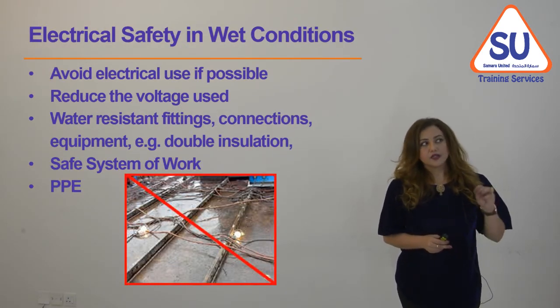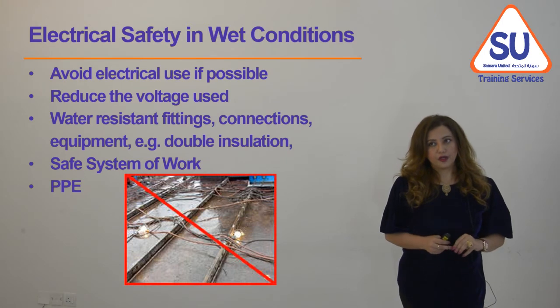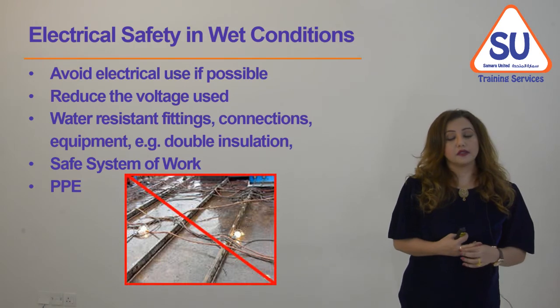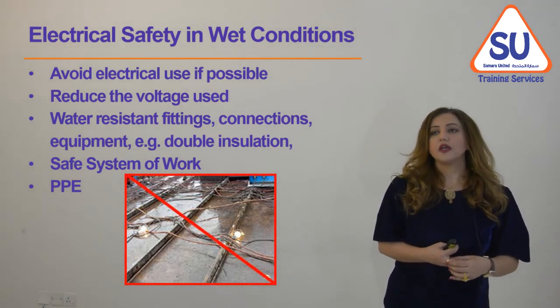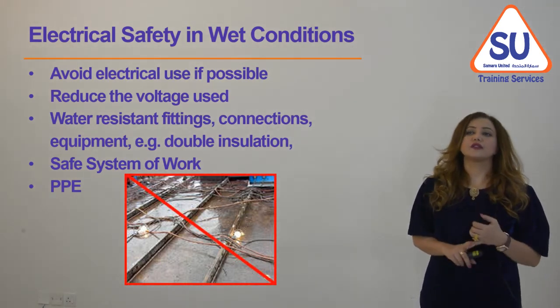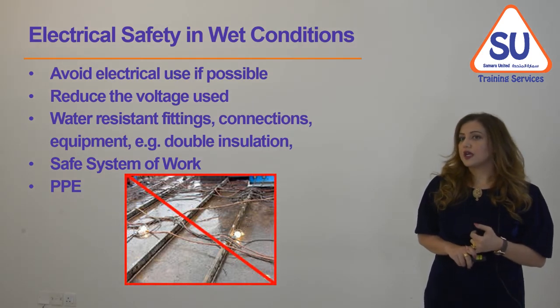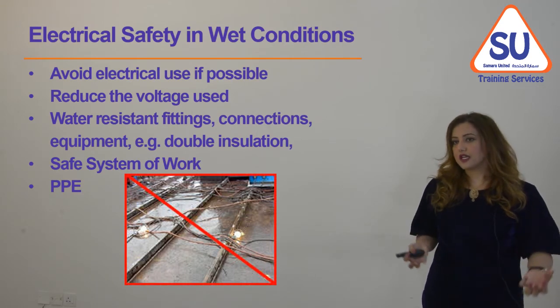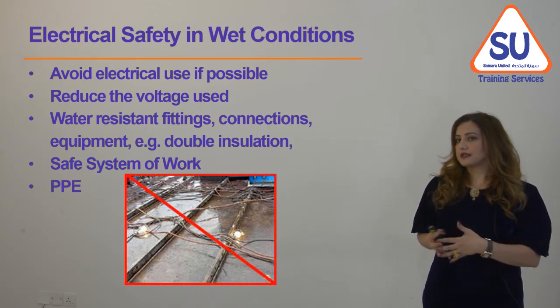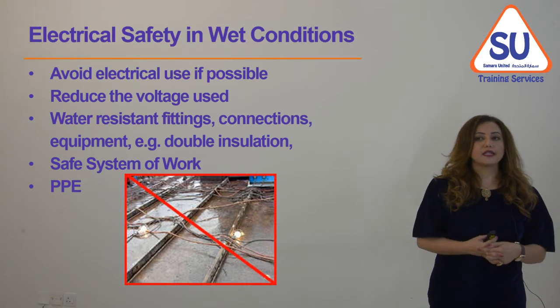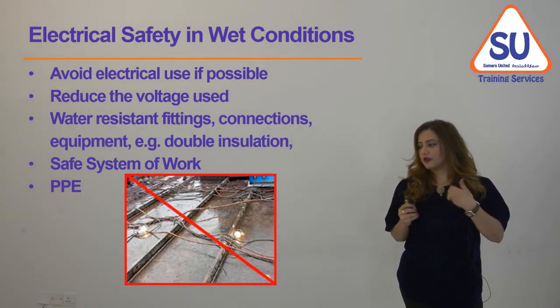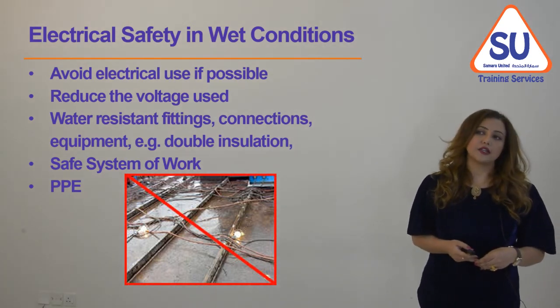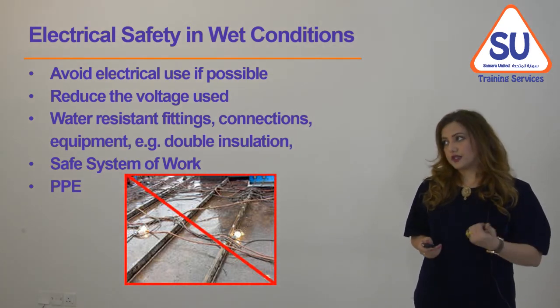Working in wet conditions is a challenge for electrical safety, and we should try to avoid that situation as much as possible. When it cannot be avoided, we reduce the voltage used, use water-resisting materials, equipment, and connections with double insulation, apply a safe system of work with the required precautions, and provide information, instruction, training, and supervision to staff, as well as the right PPE for these conditions.